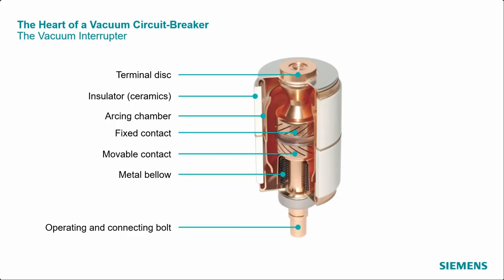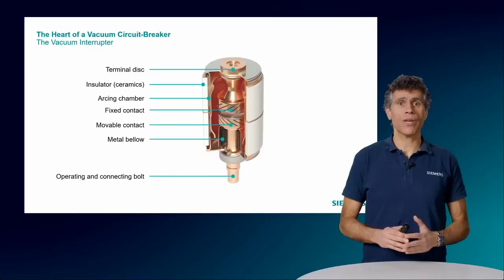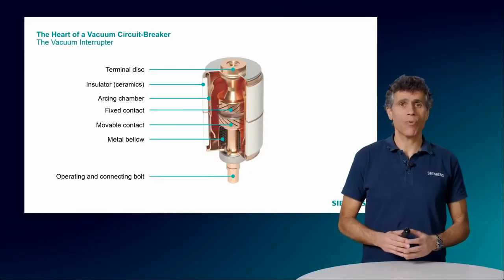When the breaker is signaled to operate, either to interrupt current or to close the circuit and allow current to flow, a force which was stored in the breaker's spring is transmitted through the connected rod and applied to this bolt, which very quickly moves the movable contact. The precise movement and control of this operating mechanism and bolts are critical as they determine the functionality of the vacuum circuit breaker, ensuring that it responds correctly and safely to operational commands.